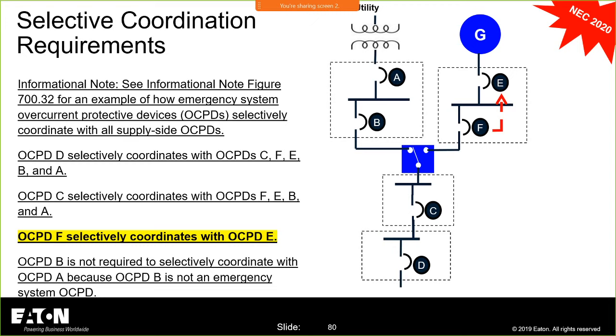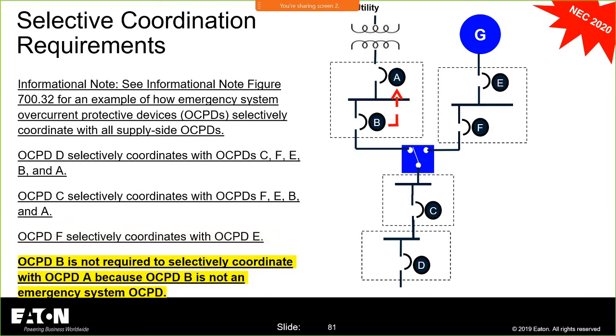Hopefully that makes sense. And then finally, you have A and B. Those two devices, although you will probably have had to make a change to accommodate the requirements that are on devices C and D, do not have to selectively coordinate with each other per the requirements of Article 700 because they do not fall under the purview of 700.